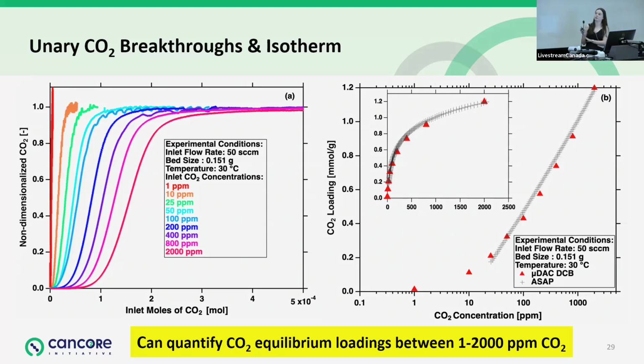The reason why we did this first without adding the complexity of the binary is we wanted to make sure that we have commissioned the instrument well and that it matches up with other techniques. The red squares here are our unary points from our µDAC DCB, the new instrument, in comparison with a standard ASAP, which uses volumetry. What you can see is we have very good agreement, so we're very confident with our system. We can quantify loadings down to 1 ppm, which means that our outlet detectors are both stable and extremely sensitive in comparison to a lot of what's on the market right now.